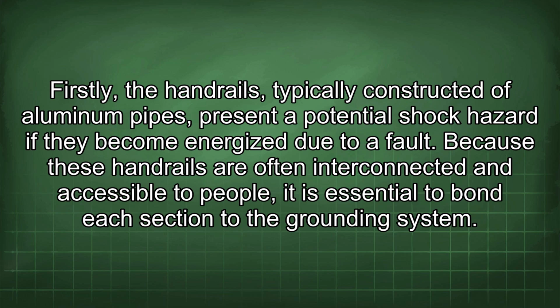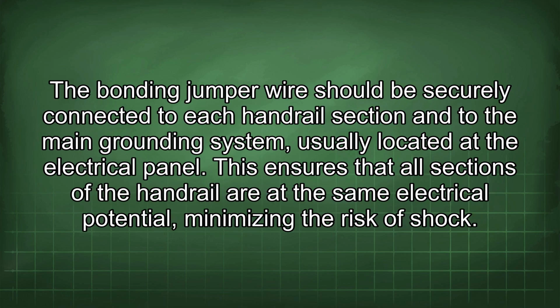Firstly, the handrails, typically constructed of aluminum pipes, present a potential shock hazard if they become energized due to a fault. Because these handrails are often interconnected and accessible to people, it is essential to bond each section to the grounding system. The bonding jumper wire should be securely connected to each handrail section and to the main grounding system, usually located at the electrical panel. This ensures that all sections of the handrail are at the same electrical potential, minimizing the risk of shock.